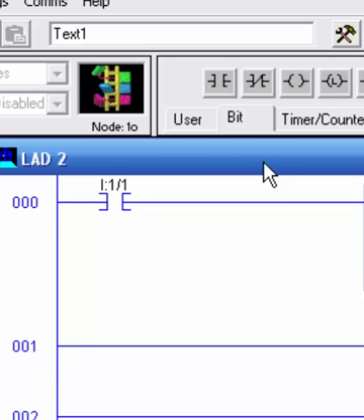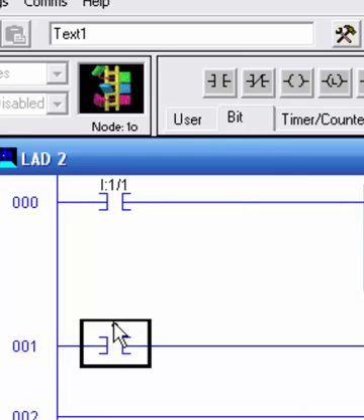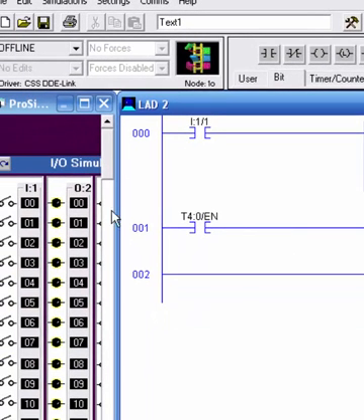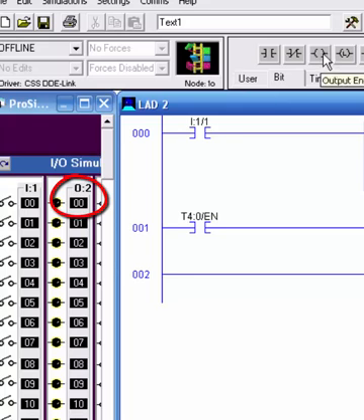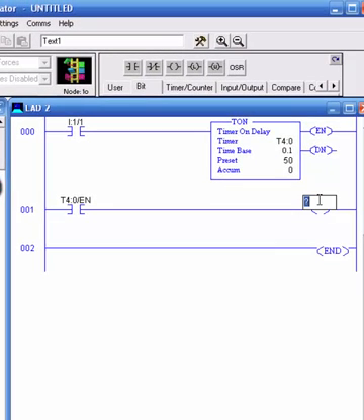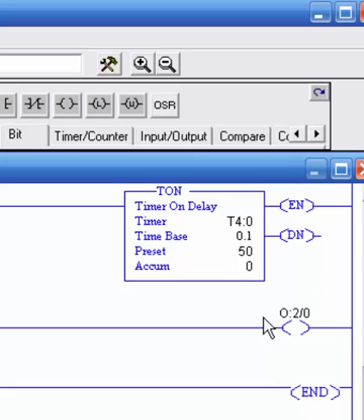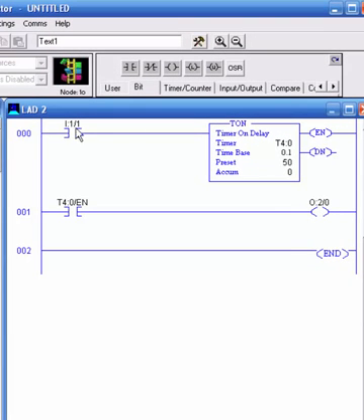As the timer is counting up in the accumulator, we may want to monitor several of the bits of the timer. If you want to monitor a bit, you would say T4:0/EN to look at the enable bit. When this is activated, let's turn on output light number two - I'll grab an OTE. I'll put O:2/0, and this will be the enable light. That light will come on as long as this switch is closed and the timer is enabled.